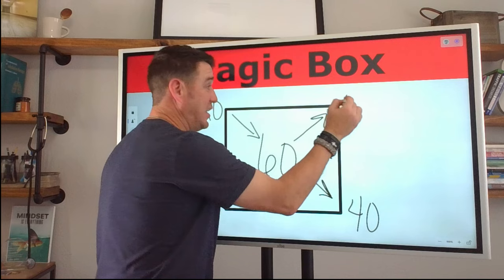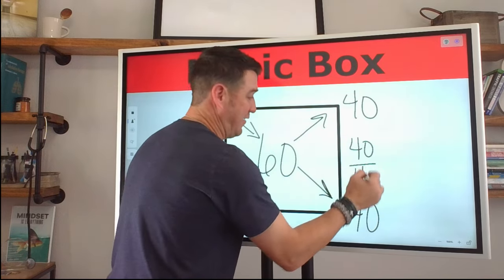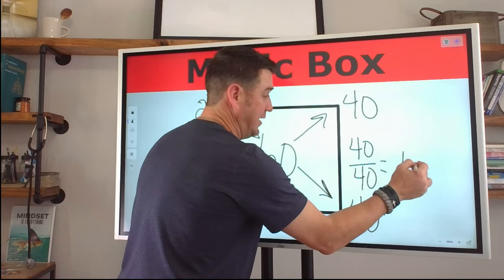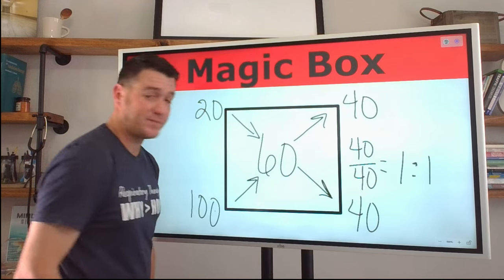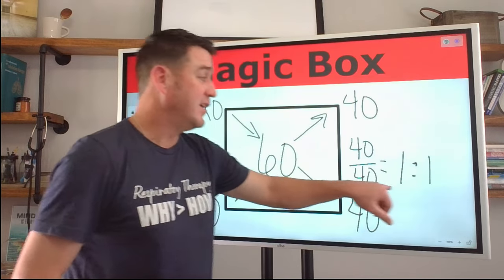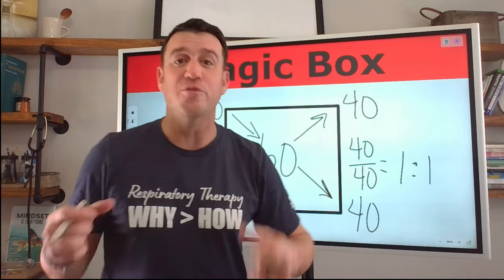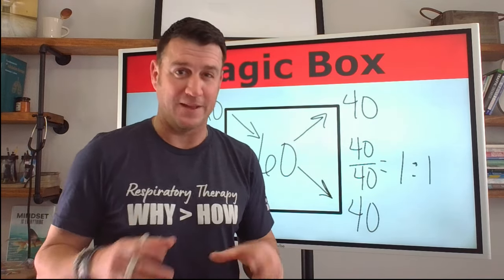100 minus 60 is 40. So now we just divide 40 divided by 40 equals one to one for every one part of oxygen that you're delivering. You're bringing in another liter of room air. And that's how that looks.